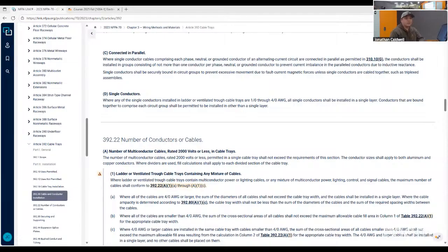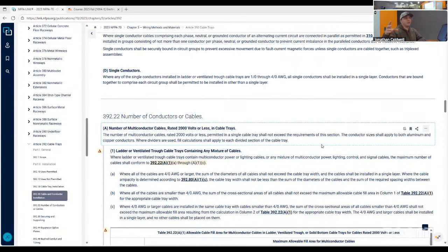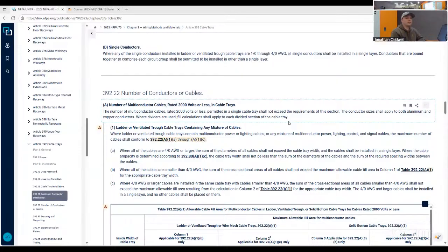Does that make sense? So for my coworkers, if you worked at the project, as you can see above the switchgear and the MCCs, they're all in one layer, right? They're not crossing, not going over top of each other. And that is because of this. And even though the manufacturer specifies that what we're using is a cable, it is still single conductors just twisted together. That is why we are still doing what we're doing.